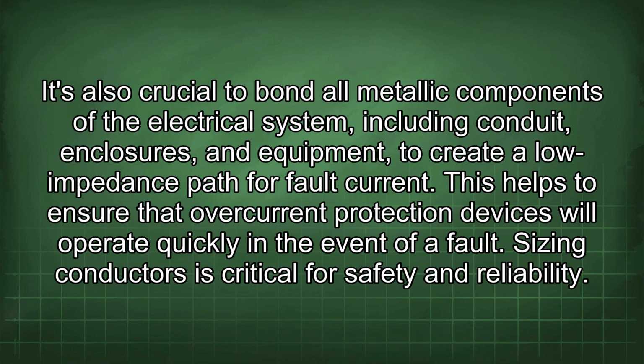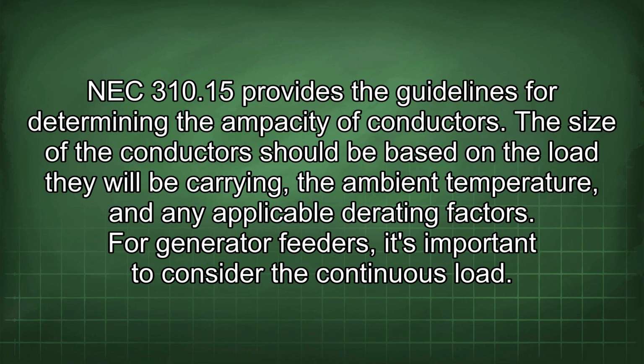It's also crucial to bond all metallic components of the electrical system, including conduit, enclosures, and equipment, to create a low impedance path for fault current. This helps to ensure that overcurrent protection devices will operate quickly in the event of a fault. Sizing conductors is critical for safety and reliability. NEC 310.15 provides the guidelines for determining the ampacity of conductors. The size of the conductor should be based on the load they will be carrying, the ambient temperature, and any applicable derating factors.